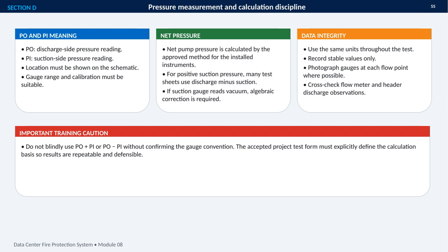Data integrity is equally important. I need to use consistent units, record only stable readings, and photograph the gauges at each flow point whenever possible. I should also cross-check the flow meter reading against observations at the header discharge. Most importantly, I must not assume that PO plus PI or PO minus PI is correct. The approved project test form needs to define the calculation basis explicitly, so every result is repeatable and defensible.